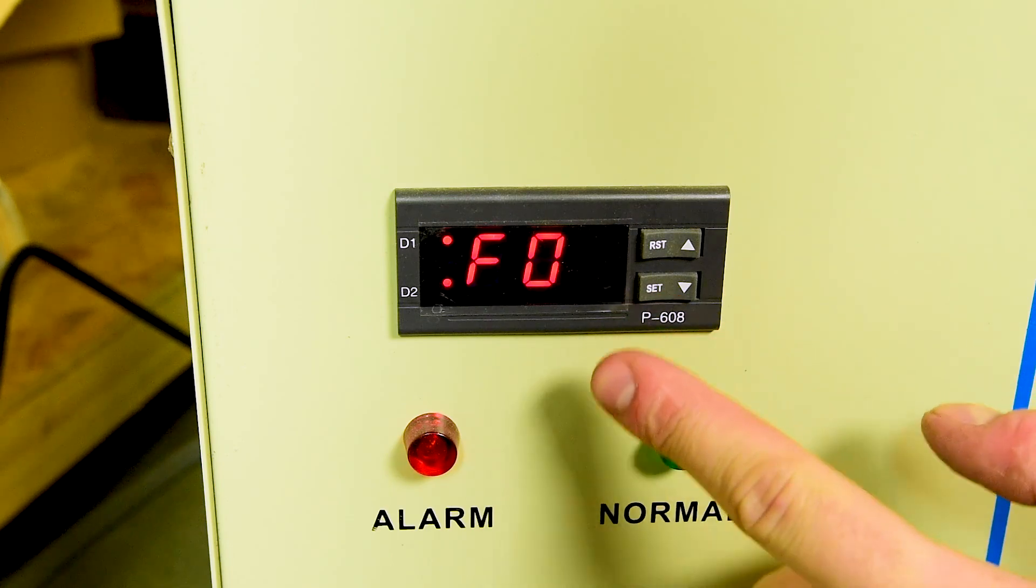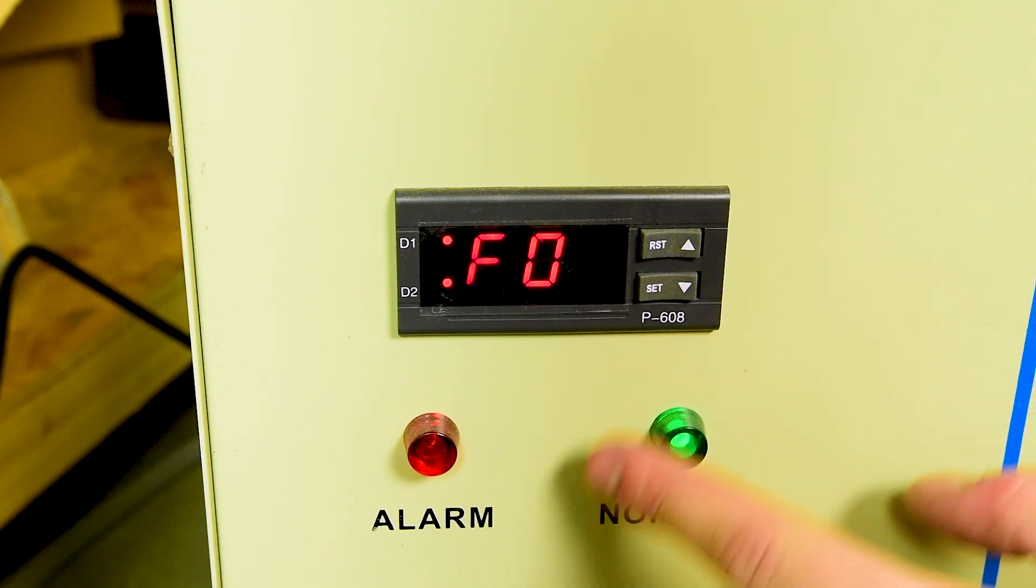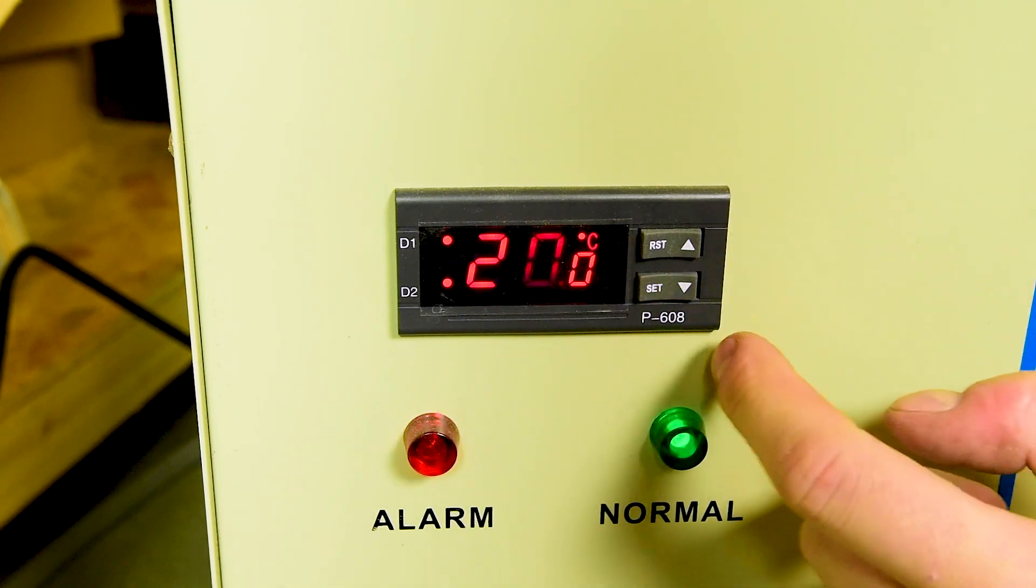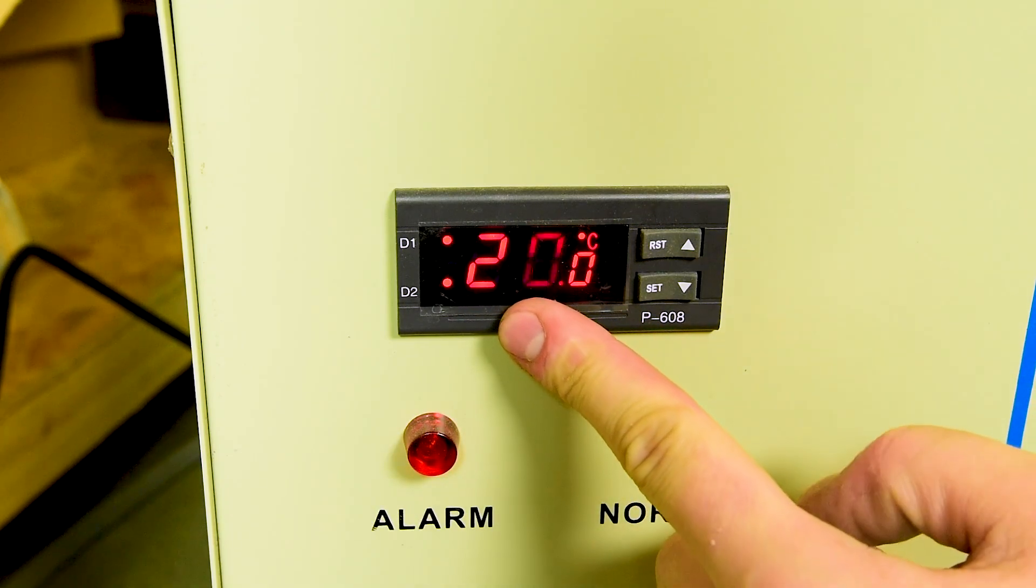F zero is what temperature we want it to be set to but if you want it set lower than 20 degrees you're first going to have to go down to function nine and we're going to change that one because it will not go lower than this. This is your lowest temperature allowed.